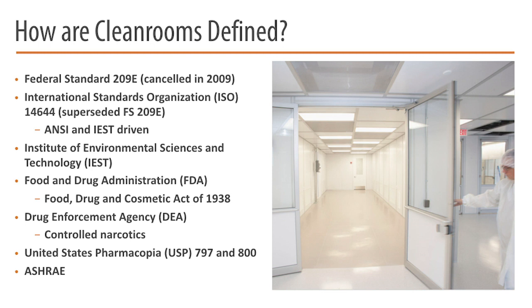Federal Standard 209E has been around forever. It was actually discontinued in 2009, but it's still referred to a lot. When you hear someone talking about a Class 10, Class 100, Class 1000 clean room, that's following the 209E standard. Since it's been discontinued, ISO 14644 is a standard that ANSI and IEST jointly developed, and that's the ISO 7, ISO 6 class, and we'll compare and contrast the two in a moment. Those really apply across the board, whether you're in life sciences or electronics. The FDA, DEA, USP, and others have other add-ons, and Jeff's going to get into those a little later, to define things as they pertain within the life sciences area itself.